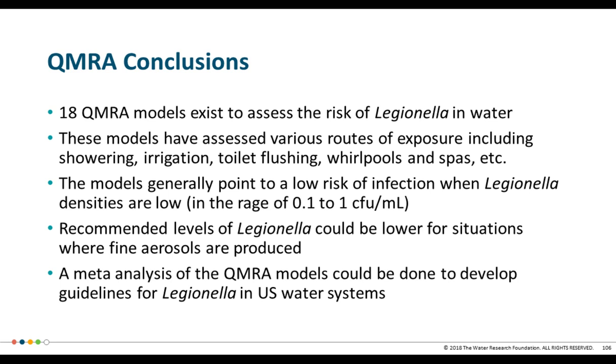The takeaway from these risk models is that there are many different models available to assess Legionella risk, covering various routes of exposure including showering, irrigation, toilet flushing, and others. The models generally point to a low risk of infection when Legionella densities are low, in the range of 0.1 to 1 cfu/mL. Recommended levels could be lower for situations producing fine aerosols, such as cooling towers, or when susceptible individuals might be exposed.